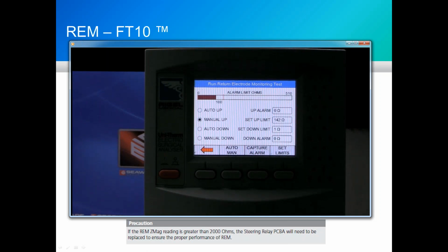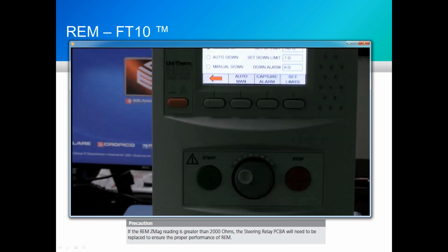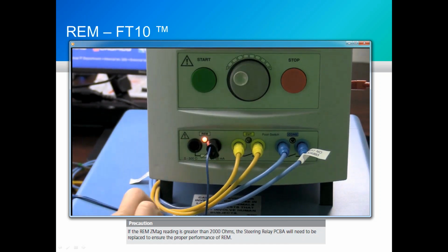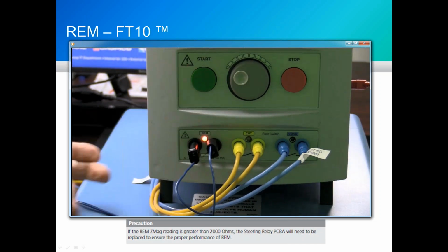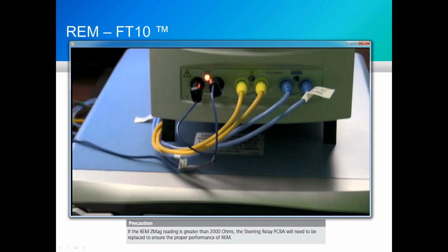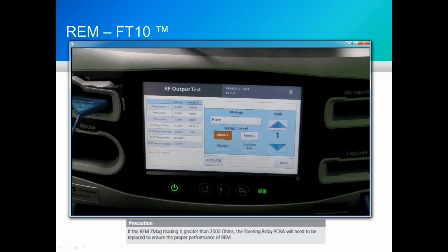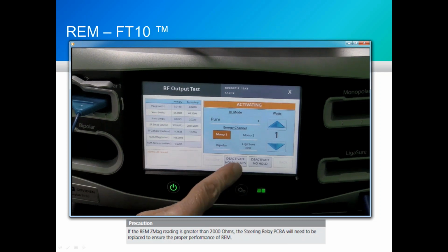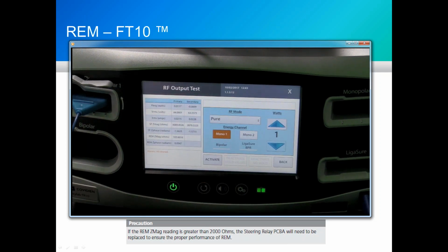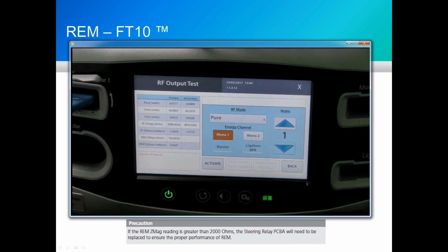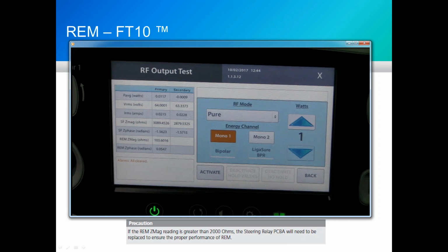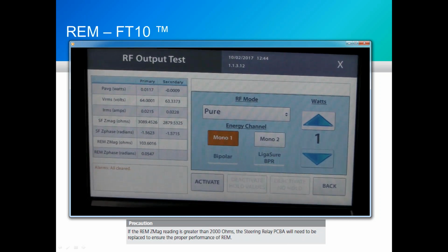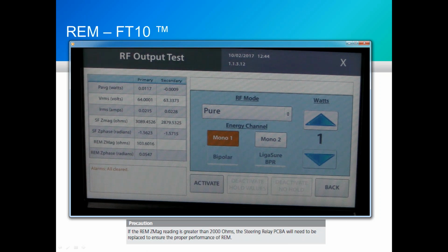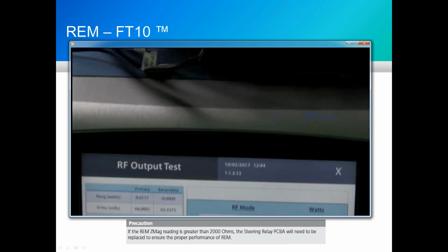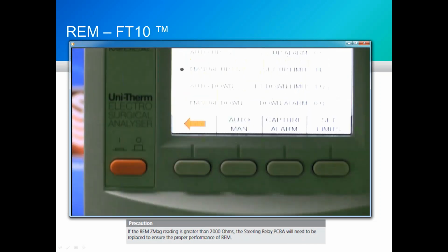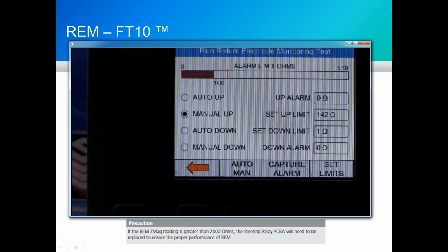So we're going to set for 100 ohms. Back down to the generator itself, making the connection now. And now back down to the generator itself, where we're just going to quickly activate the RF generator so it goes out and looks at what the patient return monitoring resistance is. And you see that we measured on the display 103.6 ohms. Now we're going to set the Unitherm to 50 ohms.